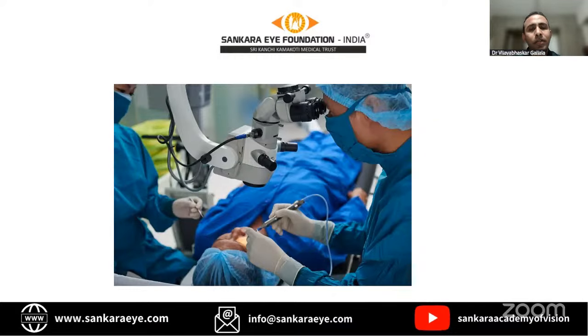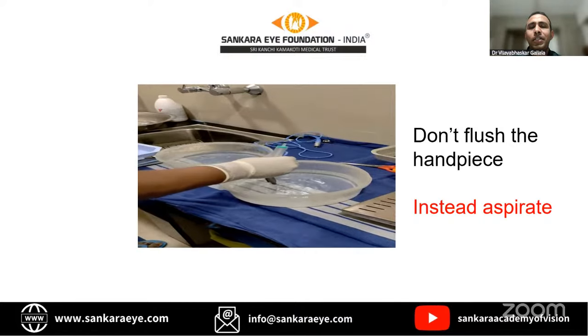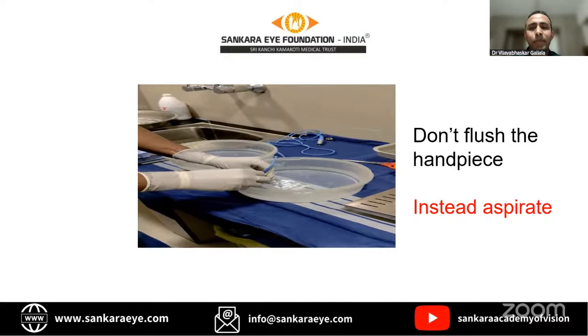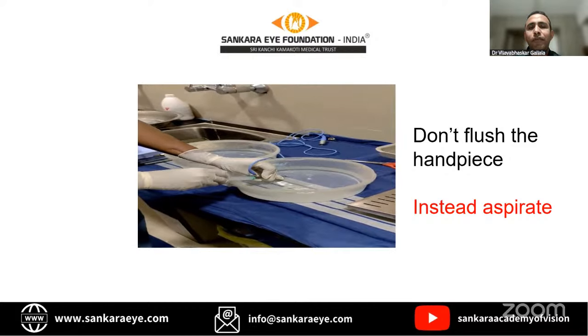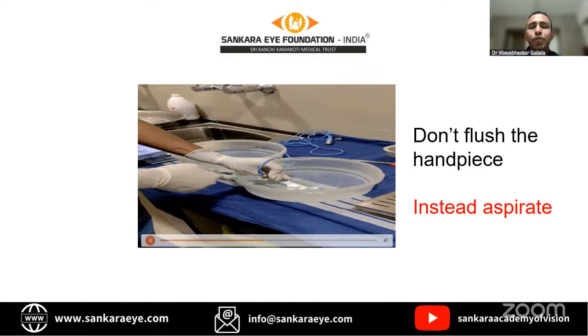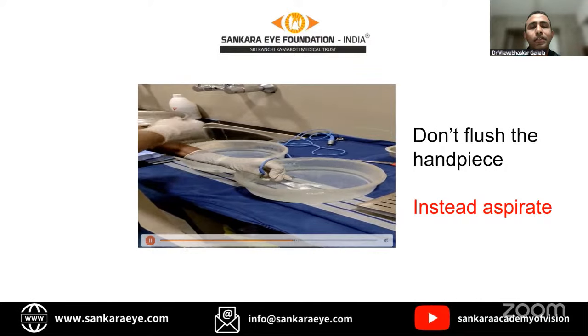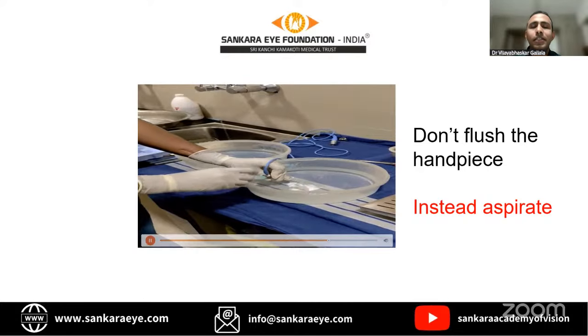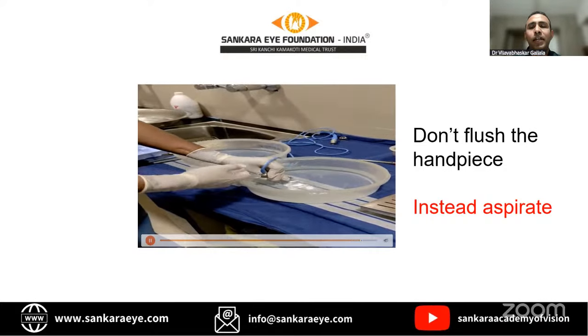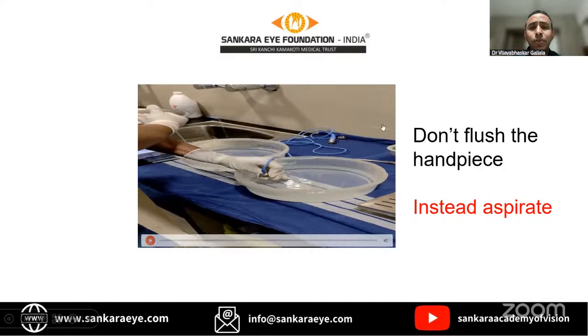And the most commonly used instrument, that is phaco. So we should take special care when cleaning the phaco handpiece. You do not flush the phaco handpiece. Instead you should aspirate it, so that you do not damage the crystals and the inside surface of the phaco handpiece. And make sure the motor and the cable are kept away from this bin, and try to avoid them becoming wet.